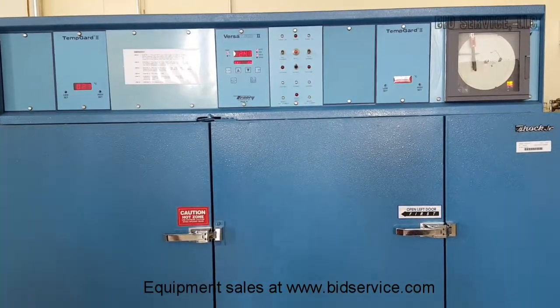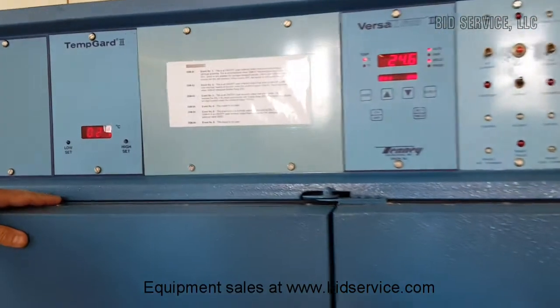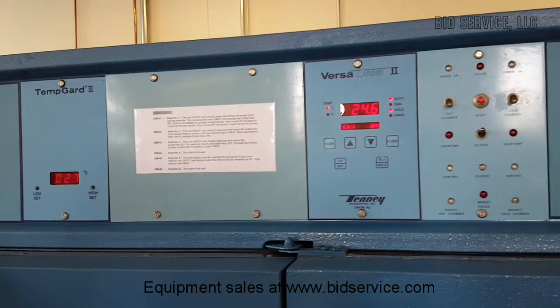This is the video demonstration on the Tenney T-Shock Jr. Here you have a TempGard for the heat chamber — it's a low set point, high set point. If it goes above or below, it will alarm.